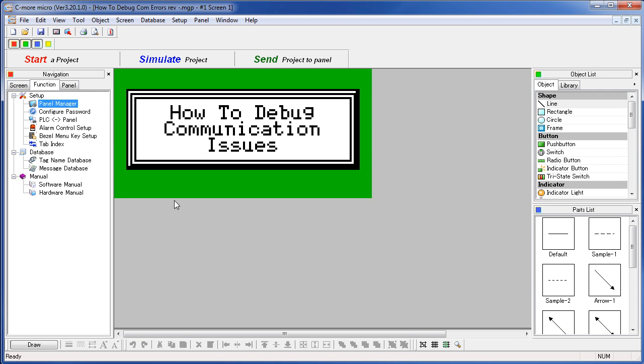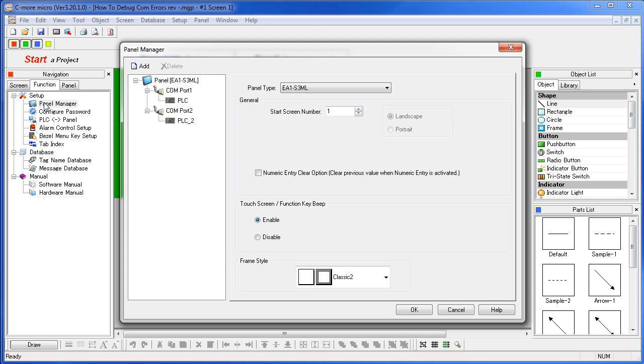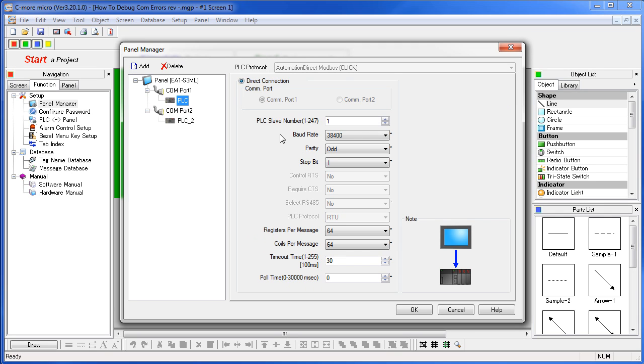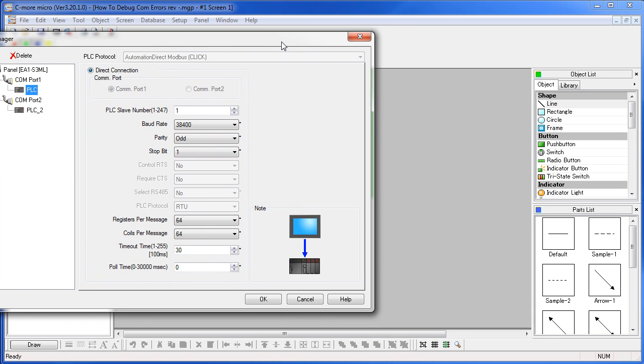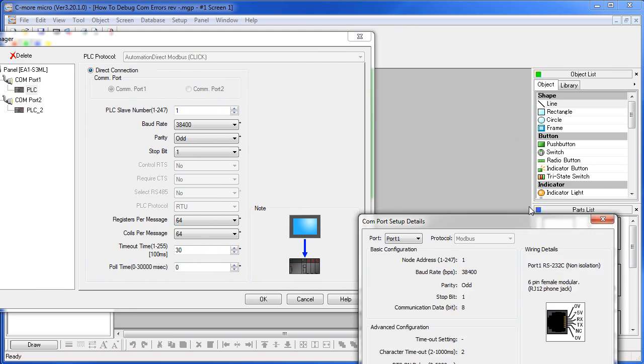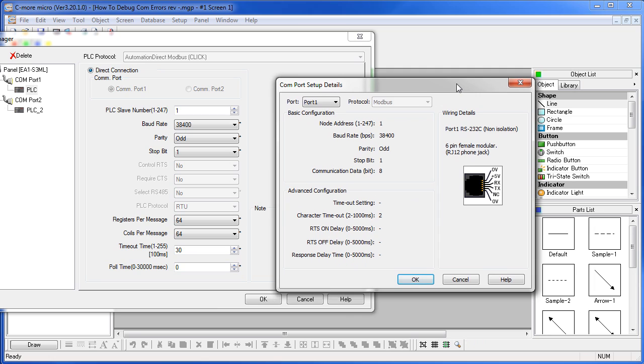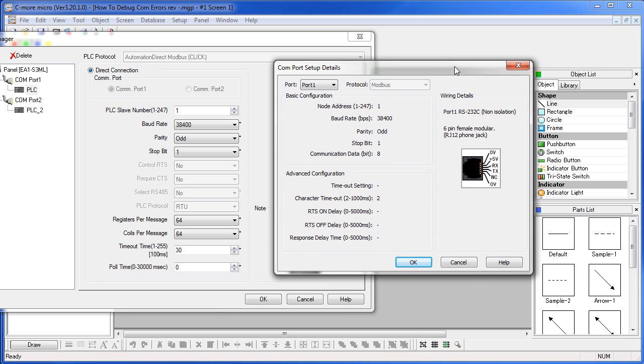Number 3: Verify that the C-more Micro's COM port settings match the COM port settings of the PLC project. Let's bring up the COM port settings for our panel. That is under the Navigation Windows Function tab, Panel Manager. We click on the device connected to COM port 1, which is the one we are interested in right now, and we see all of the COM port parameters. Keep in mind, these are the COM port parameters of the panel's serial port, not the PLC's. So, let's put the panel up here and bring up the COM port settings from the PLC project. This is from the CLICK PLC software.